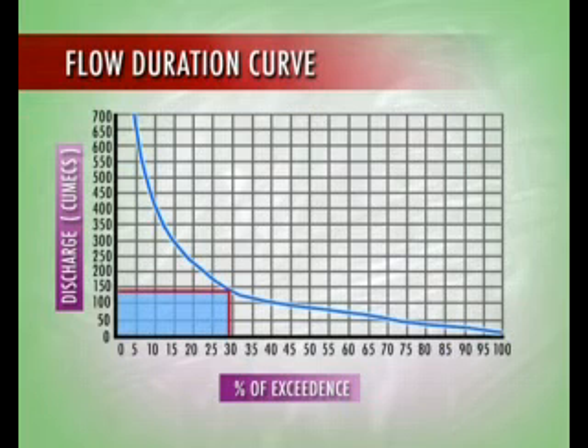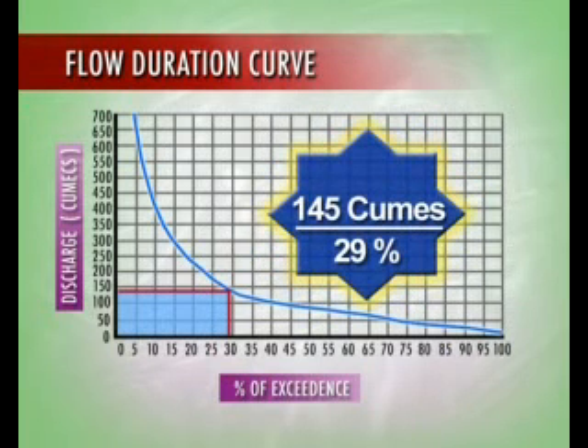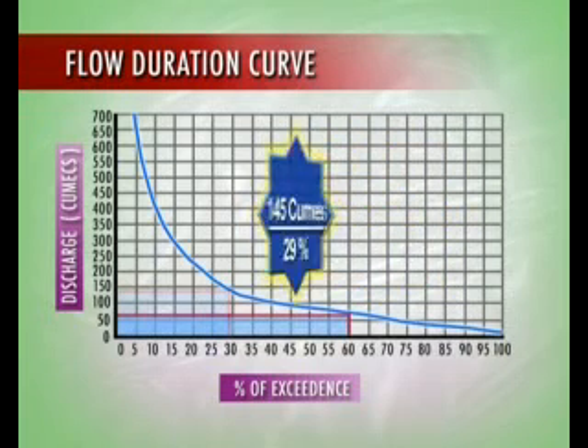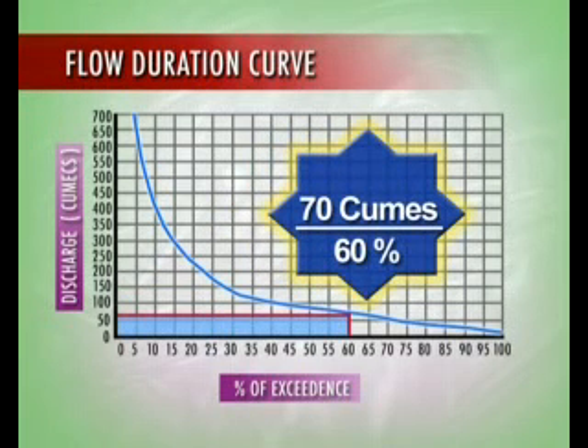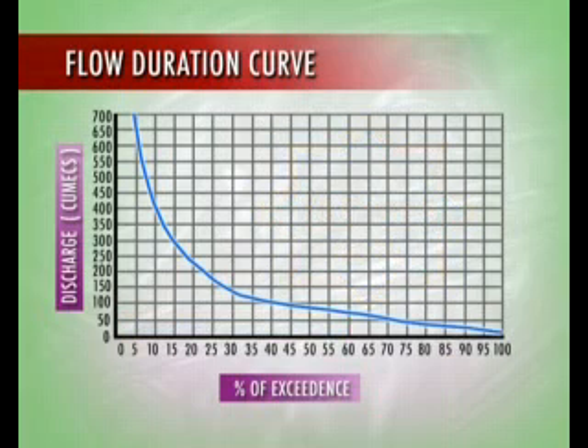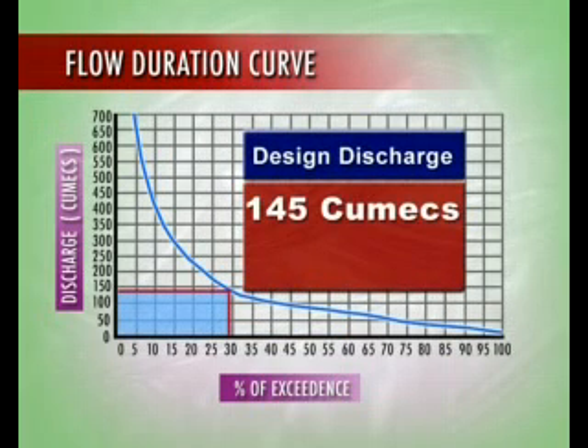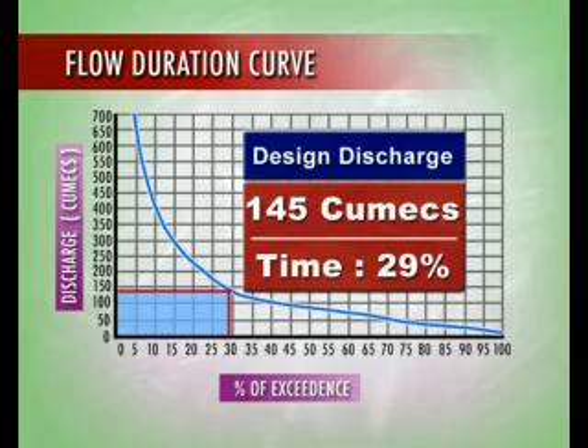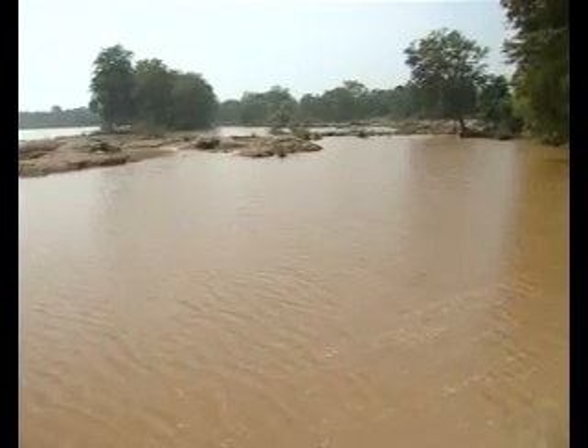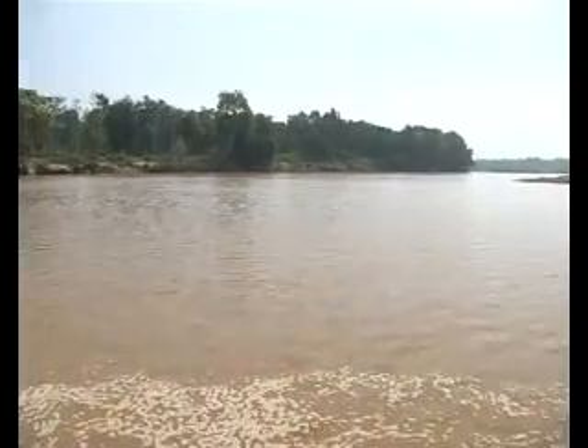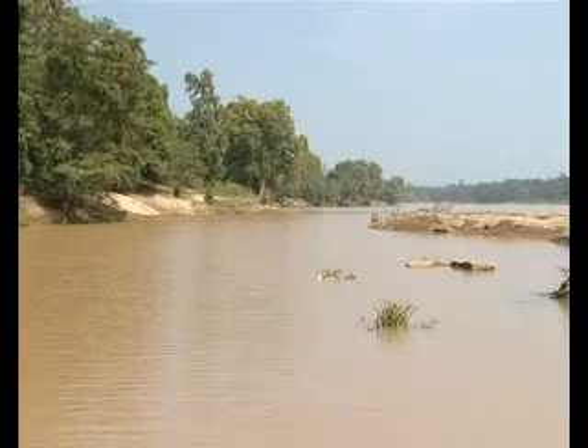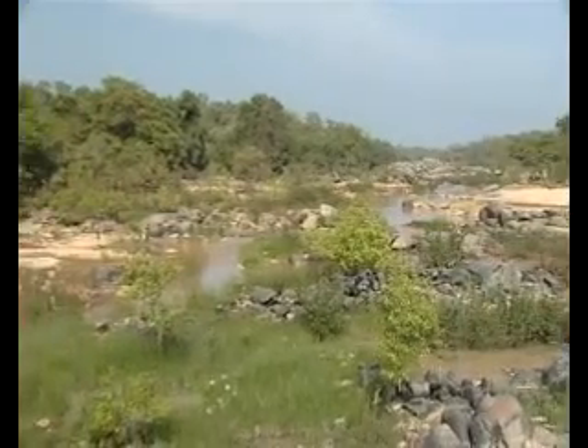It can be seen from the curve about 145 Cumecs is available for about 29% duration in a year and about 70 Cumecs is available for 60% of duration in a year. The design discharge for the scheme is therefore taken as 145 Cumecs occurring 29% of the time in a year. The present proposal is located on the right flank of the river near Tilavarti village in Dantewada district. It is proposed to generate 24 megawatts of power by utilizing the head due to level difference in the river course from the location of the pickup trench weir to tail race channel located about 2.5 kilometers downstream of the proposed trench weir.